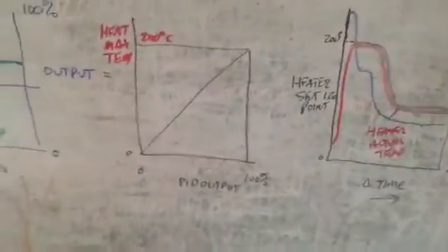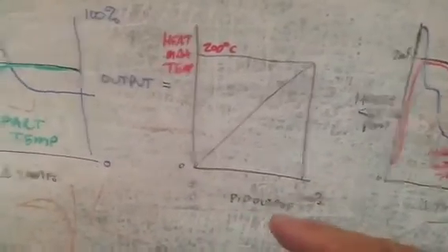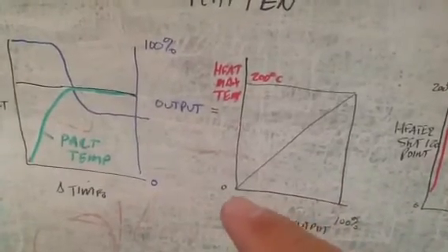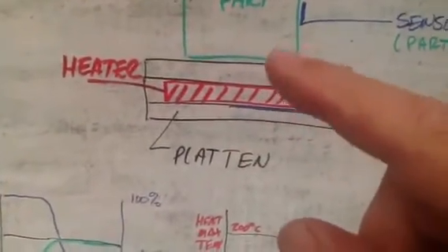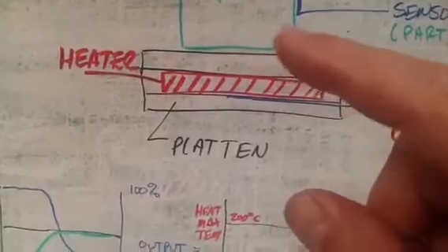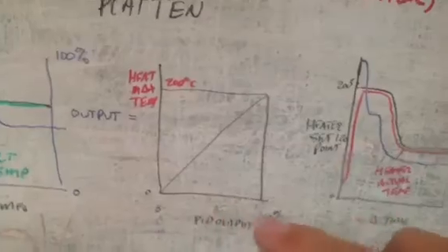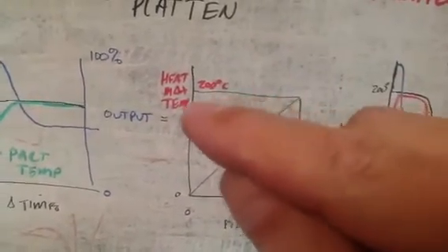So what we're going to do is this: this is just a real quick linear calculation of PID output. So this is the PID output here in the blue line, that's 0 to 100%, and we're going to translate that into 0 in this case, to its maximum temperature that we want the heater to see. So that in this interface, if it hits 200 degrees C, something bad could happen. So we're going to set our maximum temperature of 200 degrees C, so at 100% output on our PID, it's going to set a set point of 200 degrees C on our heater.